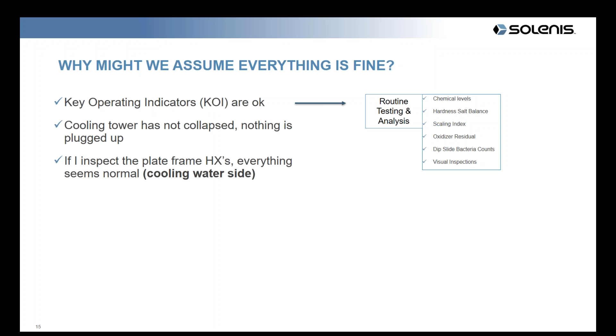And the cooling tower doesn't seem to be falling apart. It doesn't look like anything's plugged up. And if I open up the plate frame exchanger, I look at the cooling water side, and it doesn't look all that bad. Especially if I can compare it to the other side of that plate frame exchanger. So in that picture, you see the top side's the water, and the bottom side is the process. Well, the process looks pretty ugly because there's a lot of suspended solids from the mash. And that top side just kind of washes off with a hose. I don't even really need to pressure wash that, so that can't be all that bad.